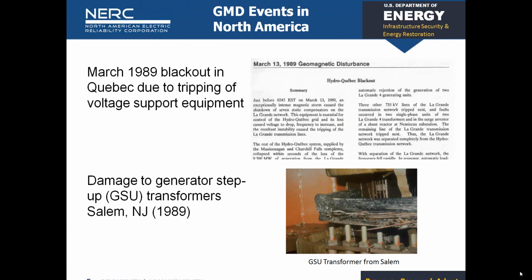And a little bit about that system. The Quebec power system is separate from our interconnection, so it's its own system. But it has some very long transmission lines that bring power down from hydro sources way up to the north. So they have some 1,000-kilometer transmission lines, and they're very high voltage, 735 kV. So extremely high voltage lines that bring that power down into the metro area of Quebec. And in March 1989, a very strong GMD event happened that caused some of the reactive support equipment around that transmission line to trip very quickly after GMD conditions started, and that resulted in a large-scale blackout.